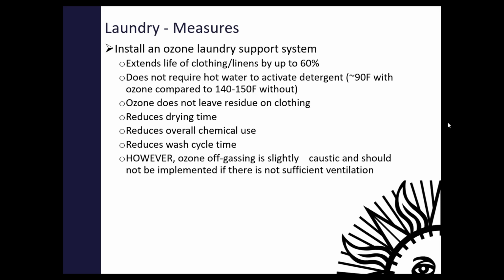But one thing you should be aware of is ozone does off gas slightly, so you can't put it in an enclosed space like a basement or something like that unless you provide sufficient ventilation. Make sure you have an exhaust shaft or duct over the unit so that you're sucking out the ozone, and make sure you have an ozone sensor in the space as well, so that an alarm will go off letting staff know they shouldn't enter. Although when your eyes are burning, you should know to leave the space.